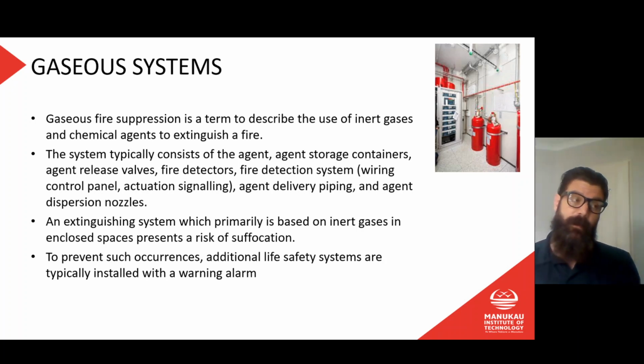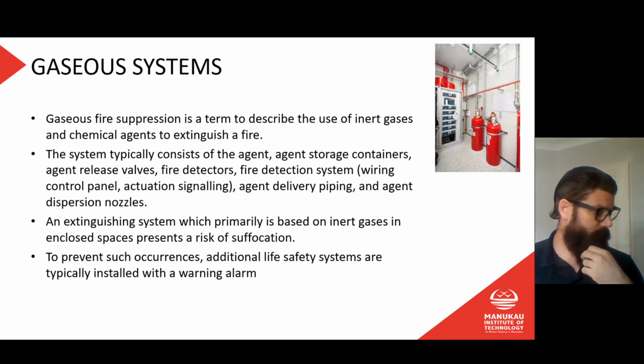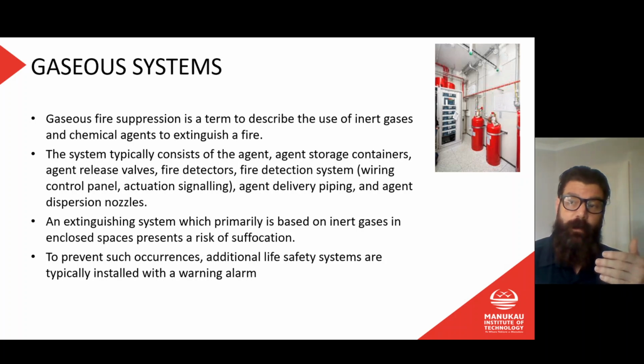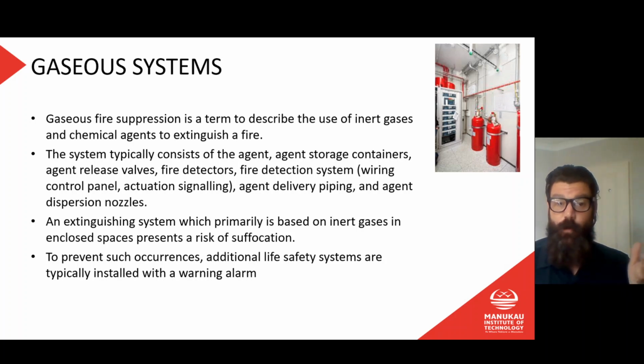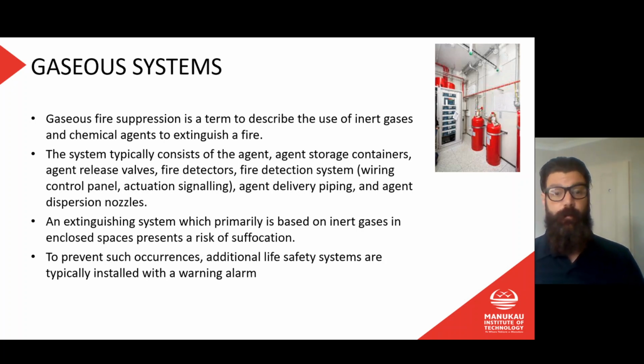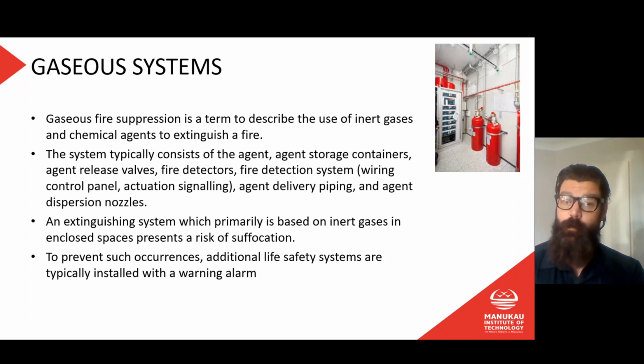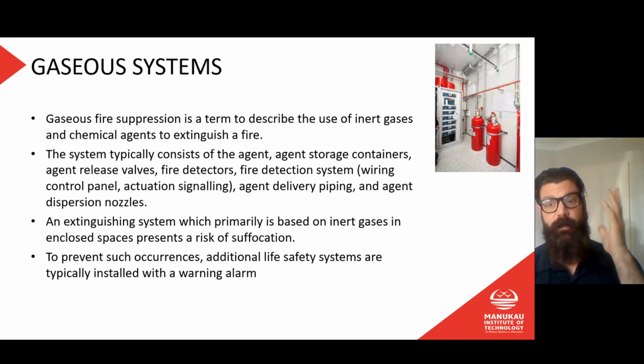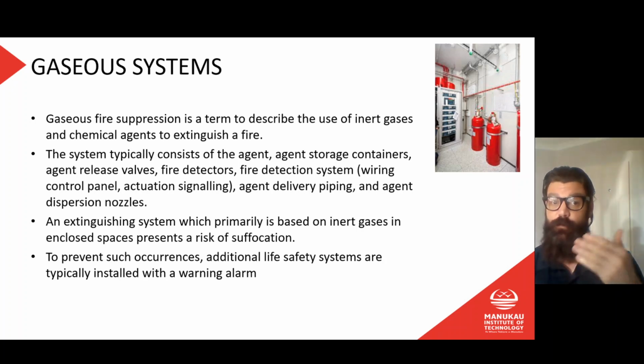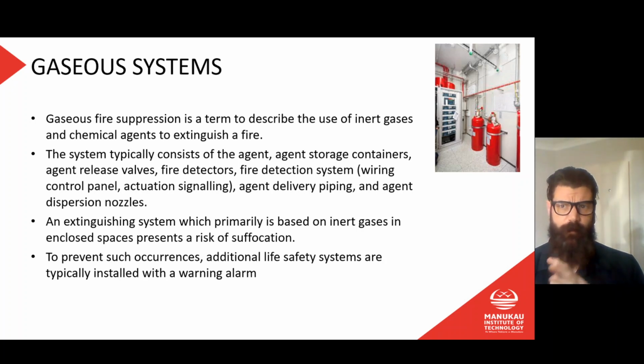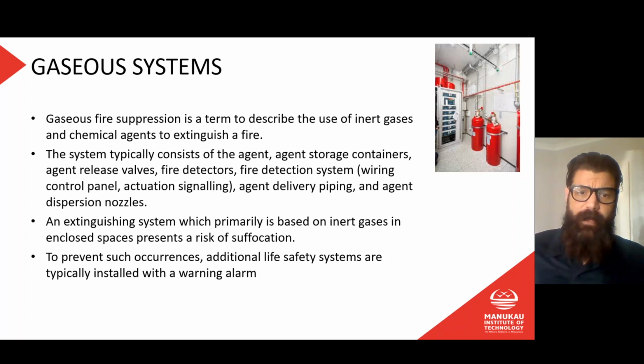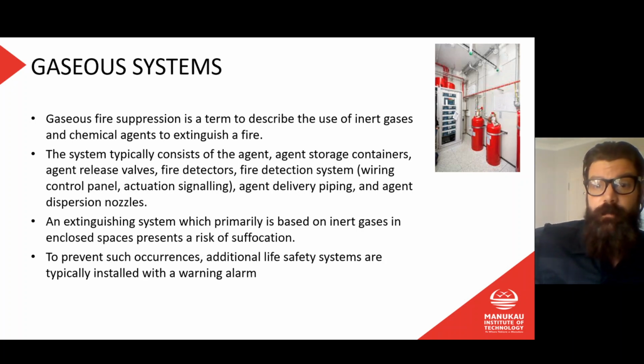As it says there, that creates a risk or hazard with regard to asphyxiation or suffocation. If you're in that room when the gas system goes off, you're going to die 100% of the time. We've got a very short period of time to get out. So generally those gas systems won't go off immediately, so they're not like as soon as the detector goes off it fills the room with gas. They usually have a delay time on them, so you have some quite complicated gas control gear associated with them.